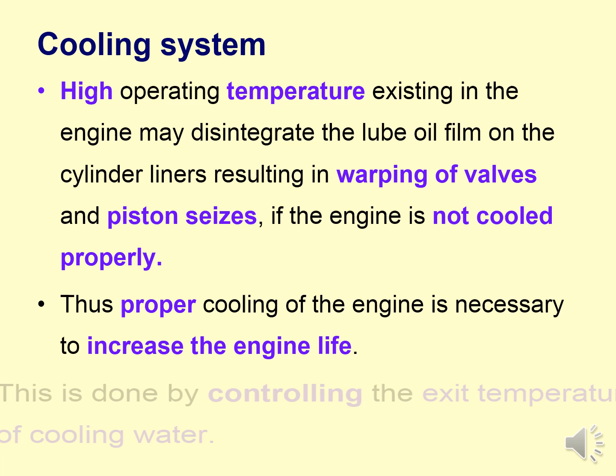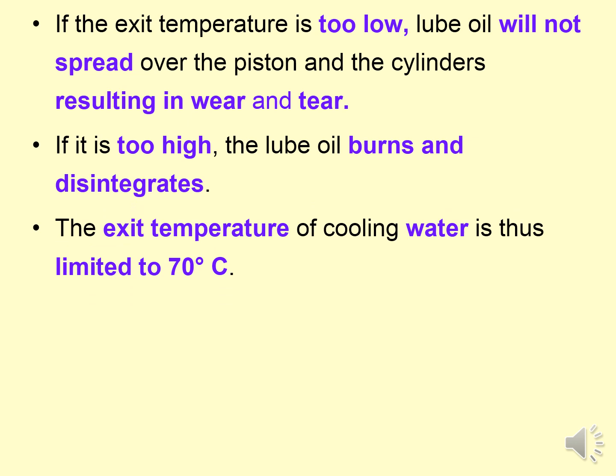This is controlled by managing the exit temperature of the cooling water. If the exit temperature is too low, lube oil will not spread over the piston and cylinders, resulting in wear and tear. If it is too high, it burns and disintegrates. So an optimum minimum temperature should be maintained. The exit temperature of the cooling water is thus limited to 70 degrees Celsius.